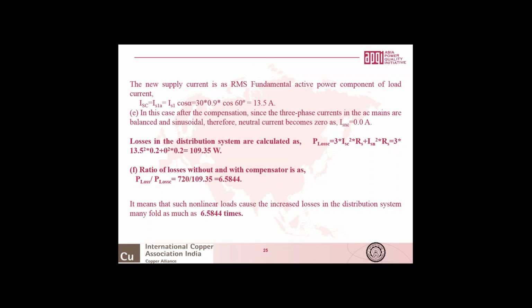So that is the very prevailing situation of excessive neutral current in the distribution system due to such nonlinear load on the 3-phase 4-wire system.